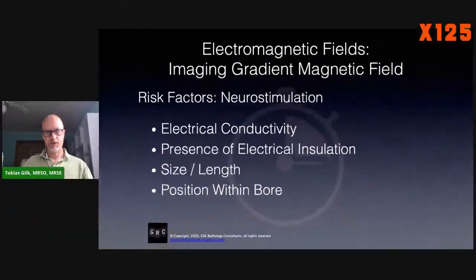So the size, the length of the object is the next risk factor. If we have a lead that winds through the patient's tissues, and we are imposing time-varying gradient energies across a large portion of the patient's anatomy, this lead has the potential to be exposed to time-varying gradients over a large area and absorb that energy over a large area. But once it turns into electrical current, what happens? Well, the only way that it escapes is through an uninsulated part of the lead. Normally the terminal ends of a lead will be uninsulated, which means we're collecting over a large area and depositing in a small area.